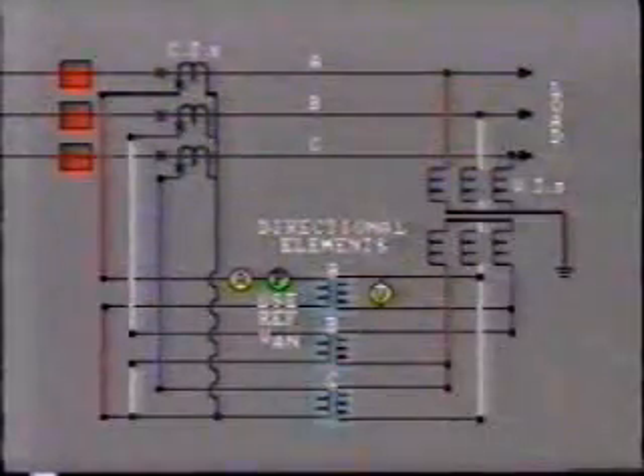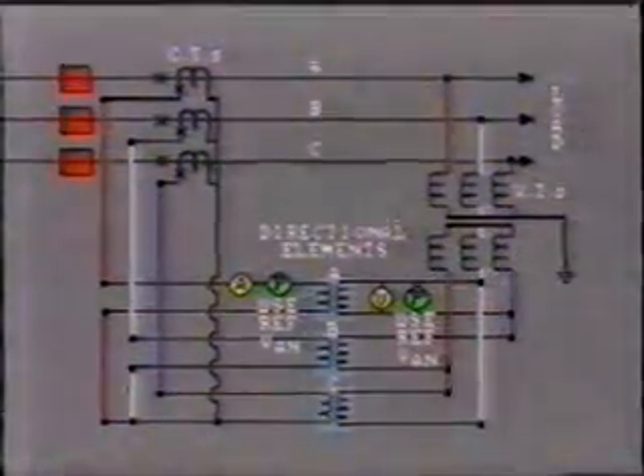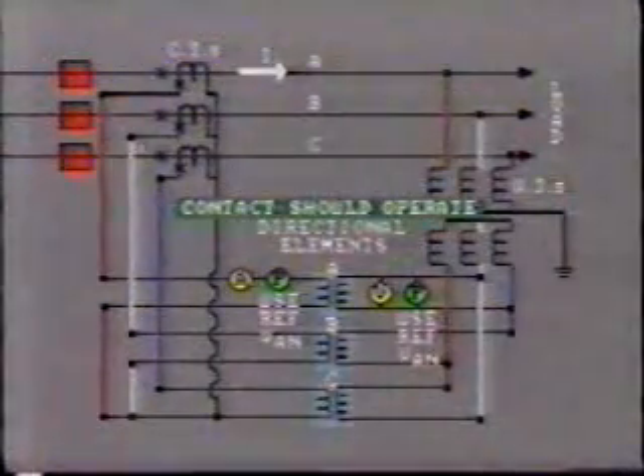To check the phase relay, the load current magnitude, direction, and power factor must be measured accurately. Also, the value of current and its phase angle provided to the phase A directional relay. The phase angle meter should use as a reference voltage the A phase to neutral VAN. If a phase angle meter is not available, a watt meter could be used with its voltage coil connected phase A to neutral. We must also accurately measure the voltage input to the relay and its phase angle relative to VAN. This will enable us to draw a phasor diagram indicating the relative phase displacements of current, IA, and the polarizing voltage. With current flowing in the designated tripping direction, usually into the line, the directional element contact should operate.